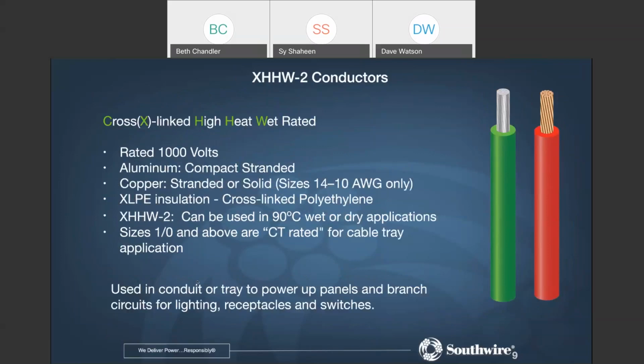The XHHW conductors, again, these are cross-linked thermoset conductors, also rated for wet locations. They're designed and NEC recognized to be used in the same applications as the THHN conductors. So why would you go with this product versus the THHN?